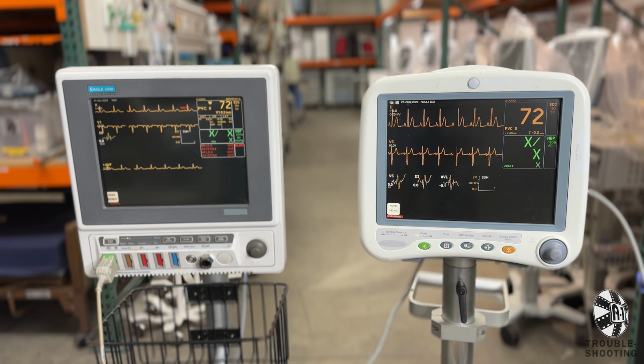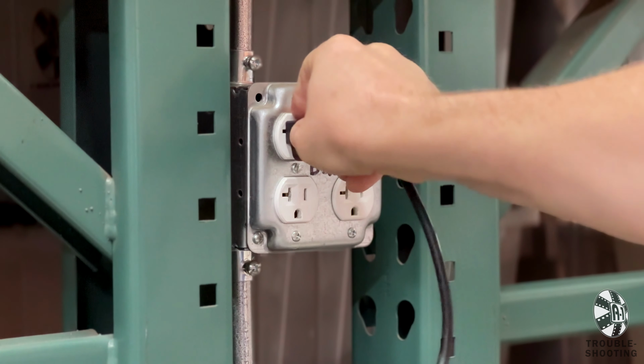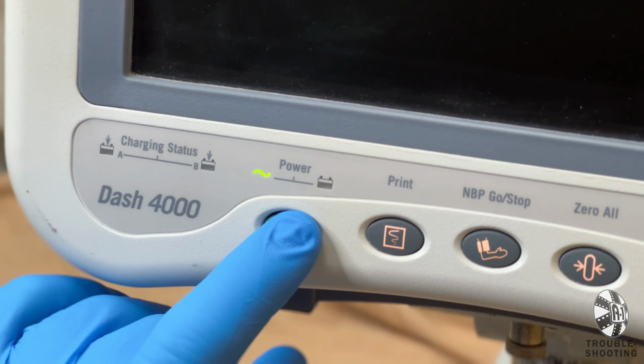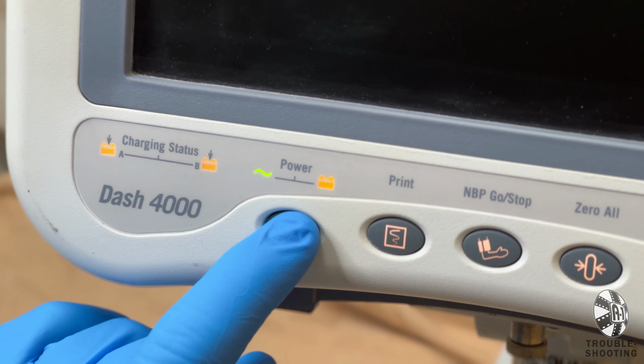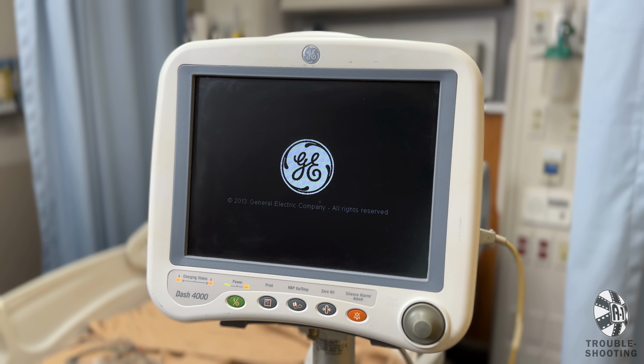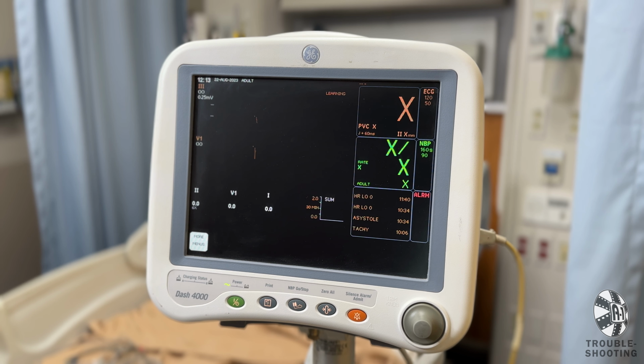The unit is not powering up. No image. For the Dash 4000 or Eagle 4000, plug the unit into a wall socket. Hold the power button on the lower left for 2 to 3 seconds. Buttons may light up and you may hear a beep. Wait 5 to 10 seconds for the screen to illuminate.